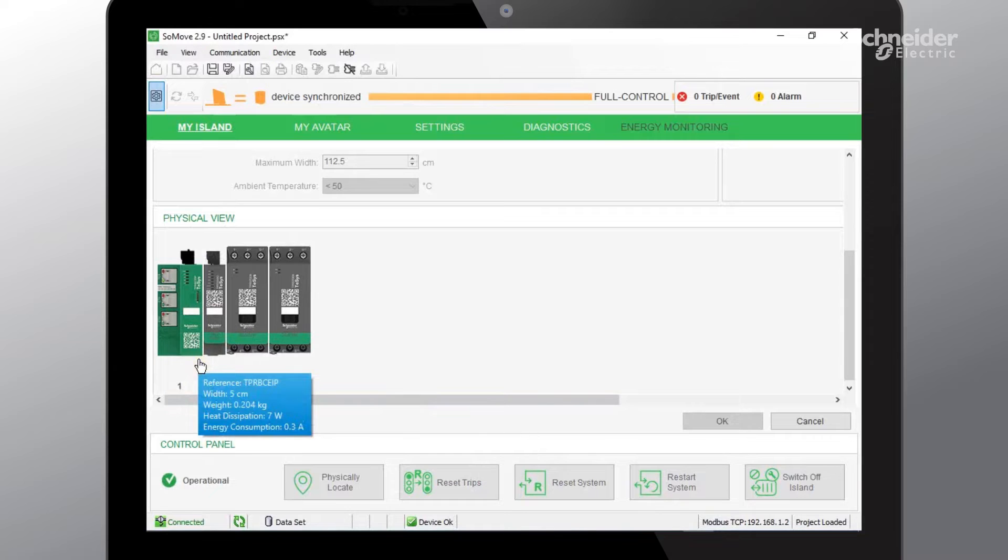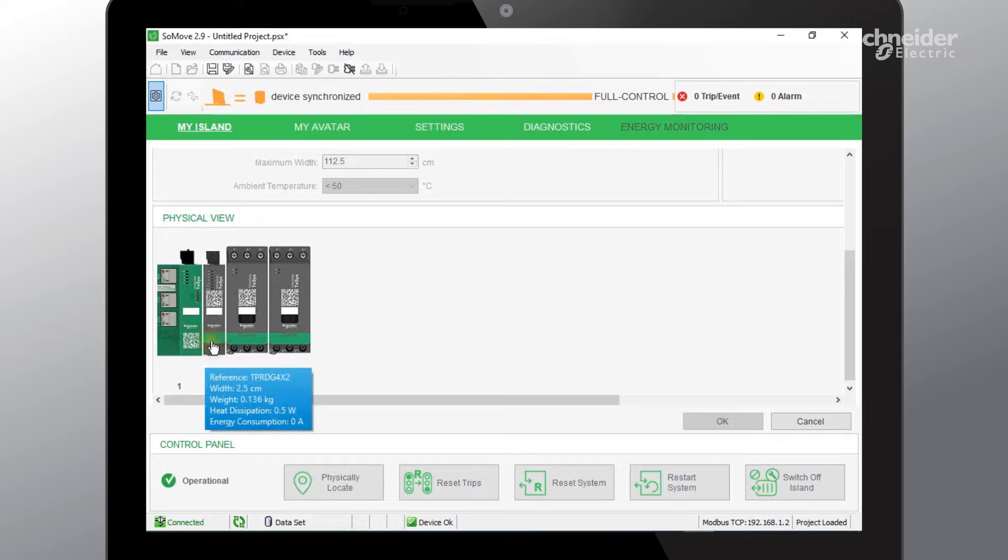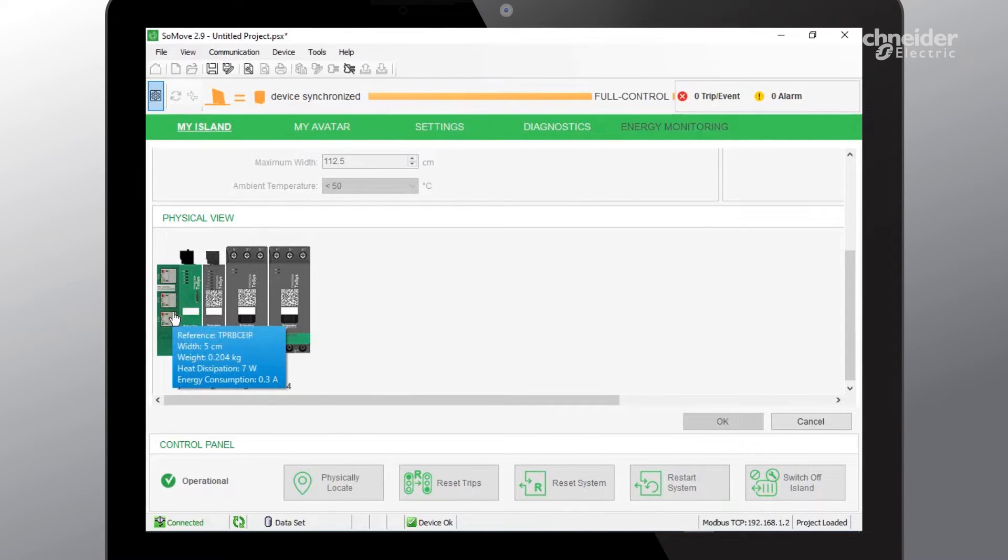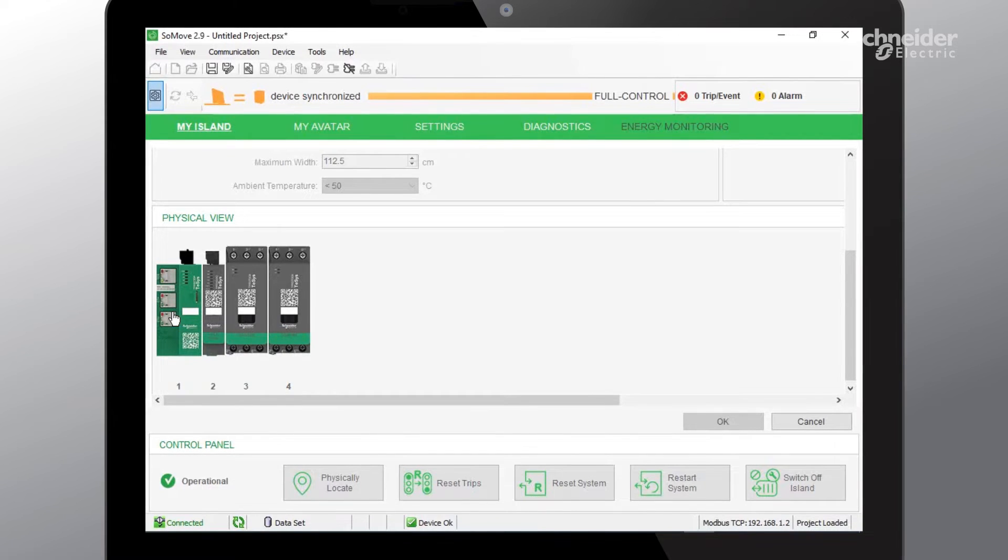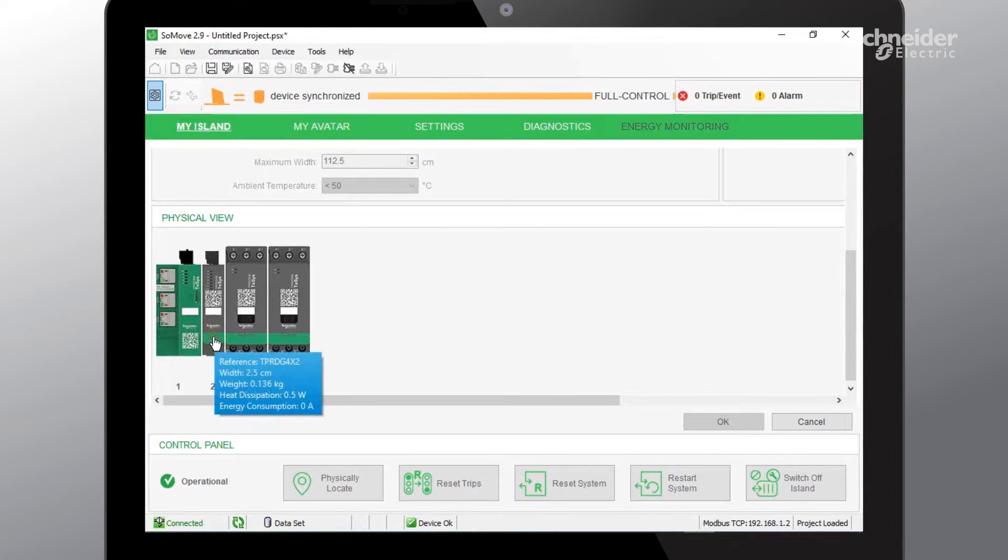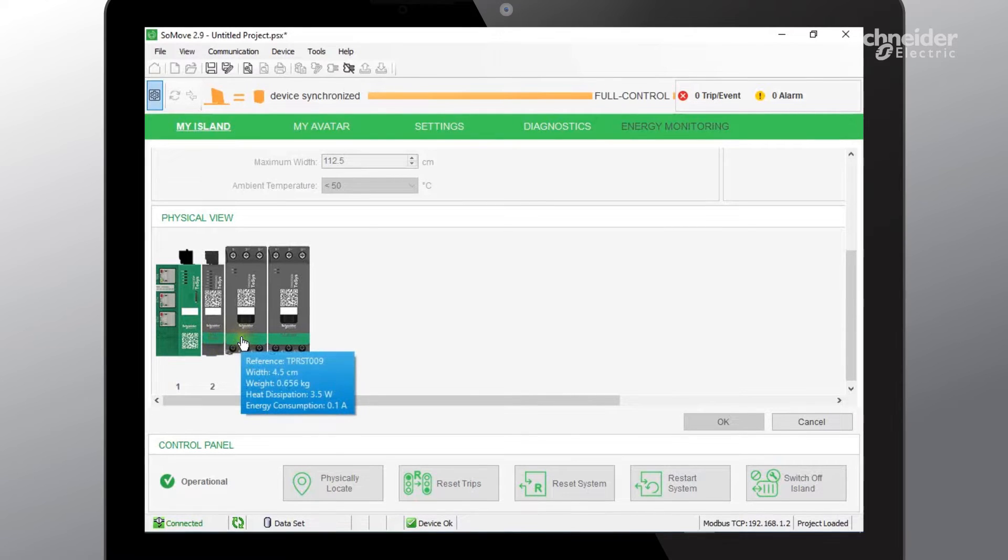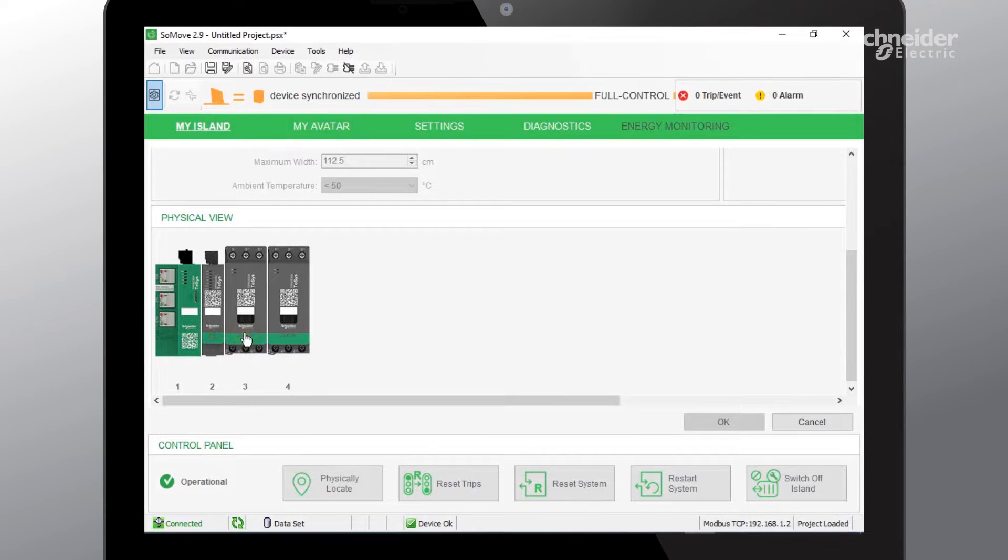In SoMove you can see that I have already pre-configured our TeSys Island configuration. In the first slot we have a bus coupler that is set up to communicate Modbus TCP IP, and in the second module we have a digital input module which allows four digital inputs and two digital outputs. And then the last two are two 9-amp motor starters that are interconnected to allow a two motor direction motor starter avatar.